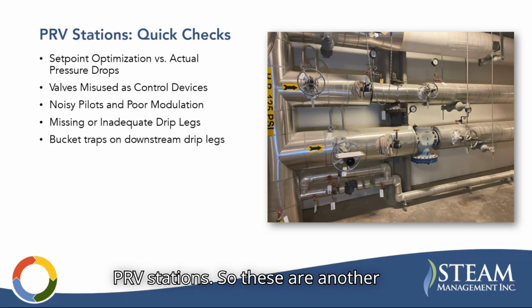PRV stations. These are another common source of efficiency issues. We often find set points aren't optimized compared to actual pressure drops. In some cases, the bypass valves get misused as control devices. Noisy pilots or poor modulation are clues to underlying problems. And then there's missing or failed drip leg traps. Often you'll see a bucket trap downstream of the PRV, which is not a good application because bucket traps require a primer of water. Downstream of a PRV, you get a little bit of superheat in the steam, and it will evaporate that water out of the bucket trap, and then it will fail to work. So there's just a lot of problems that occur around these stations, and often there's an opportunity for efficiency improvement.